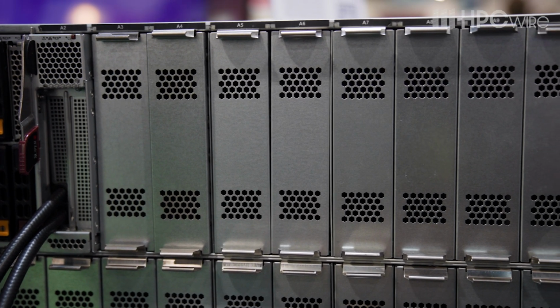All of our products here are passive, with no moving parts — just heat exchange surfaces designed for each processor, the DIMMs, the VR, and really any heat generating component in a server we can cool. Some cold plate loops just cool the CPU, some also cool the memory, and we have some fanless server designs with complete liquid cooling — 100% of the heat captured into the liquid cooling system.